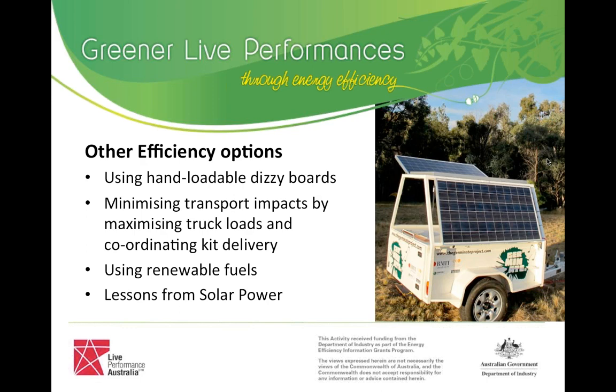Without going too far into the nuances of solar, the lessons that are relevant for diesel generators come back to the power diet: knowing in advance what people are planning to use, and if there's any doubt, checking the actual consumption of the equipment, because sometimes what people assume it's going to use based on what they've been told by a hire company is not actually what it will use.